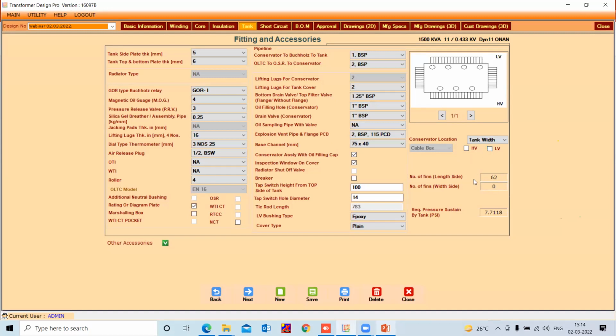Thereafter, the number of fins on length side. Now, the number of fins on width side is 0, because the tank length side area is sufficient to provide the required heat dissipation. Thereafter, the required pressure sustained by the tank in PSI, that also we have mentioned over here.